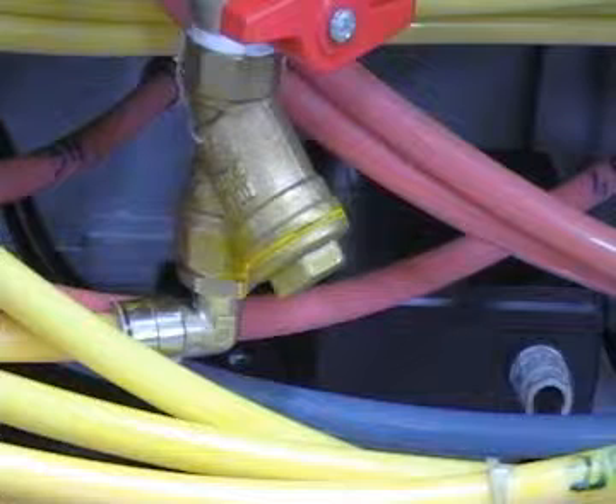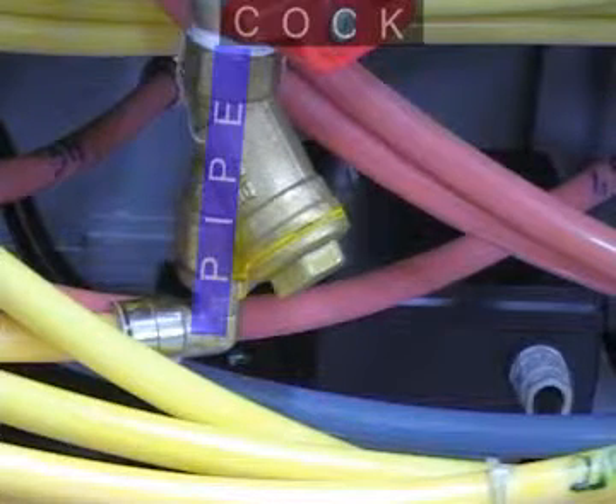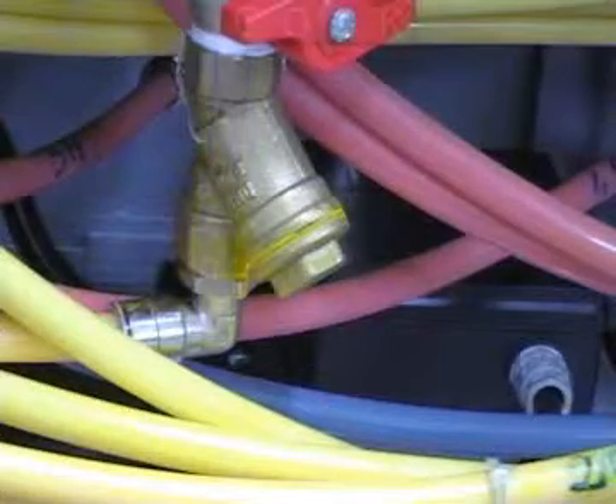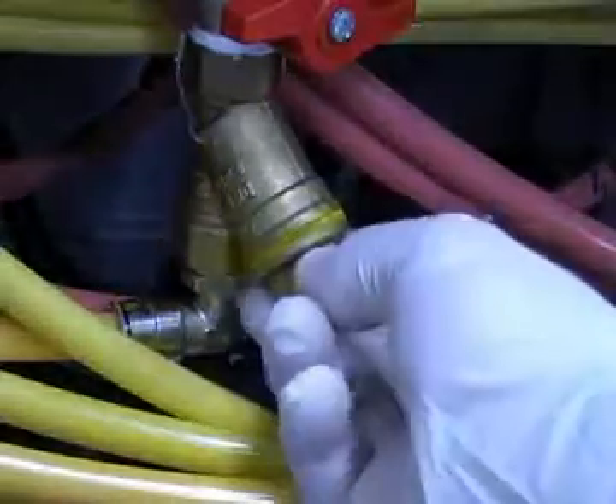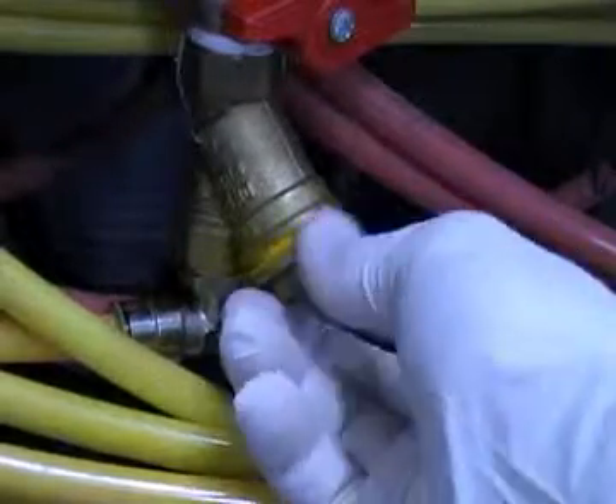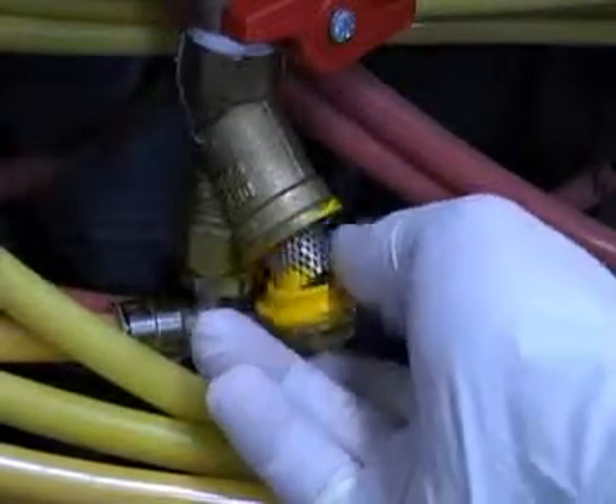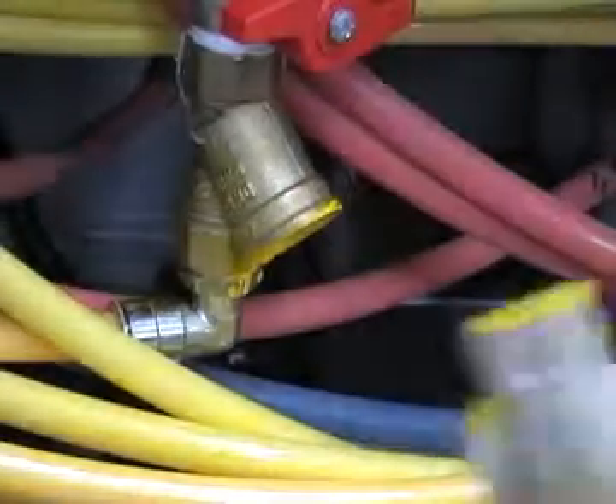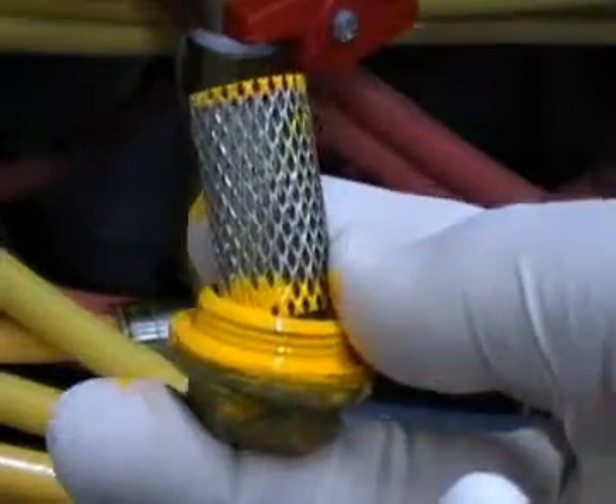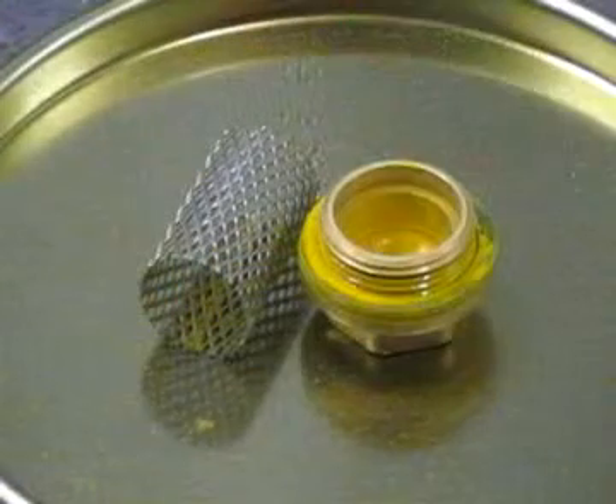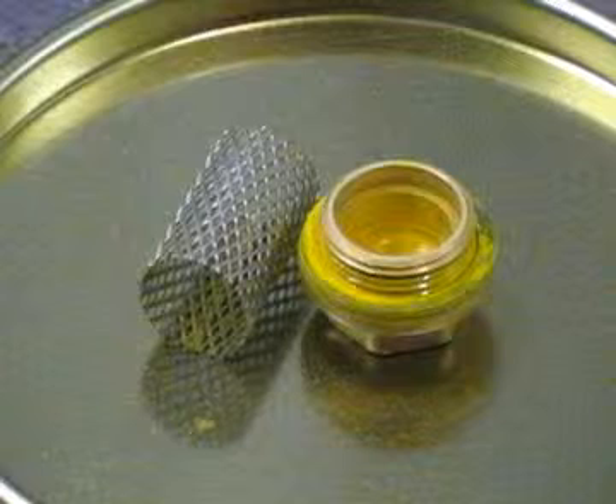Be sure the supply of colorant is turned off. Close the cock located at the outlet of the canister in the discharge circuit. The cock is closed if it is perpendicular to the pipe. Unscrew the hexagonal plug. The best way of doing this is by gripping the upwards pipe with mole grips and using a 21mm socket to unscrew the hexagonal plug. Take out the filter. It has a cylindrical shape, and clean it or change it. Finally, mount everything again. After every cleaning of the filter, we recommend turning the pumps on for 15 minutes and making a calibration of the relevant circuit.